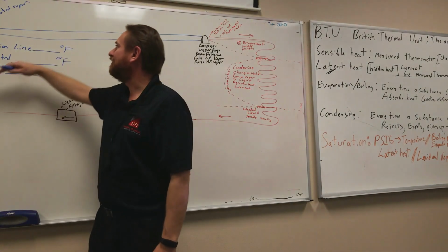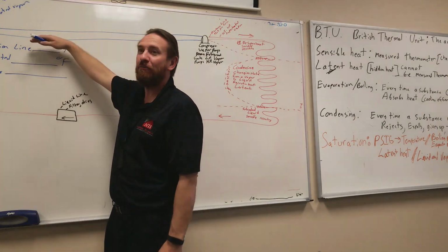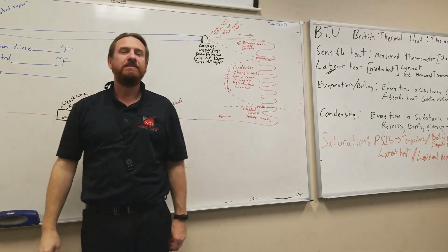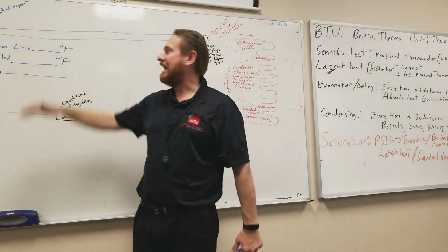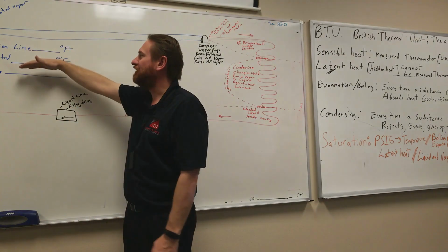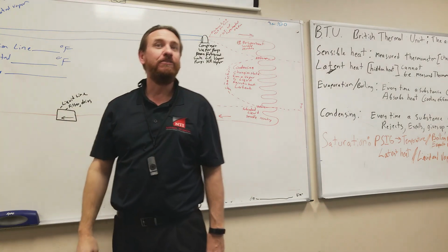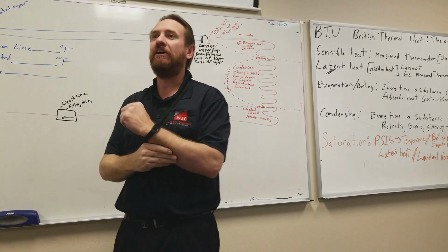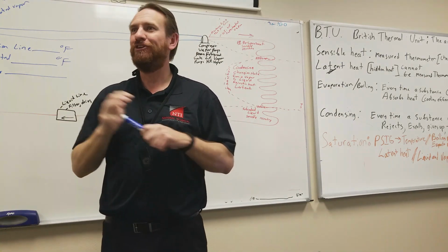Yes. So my suction line temperature should always be warmer than saturation. It's a good thing to have it in this order, so that if you get a negative number, you know there's a problem. There's something wrong, I need to find out what's going on. There's some kind of an issue. Cool, huh?